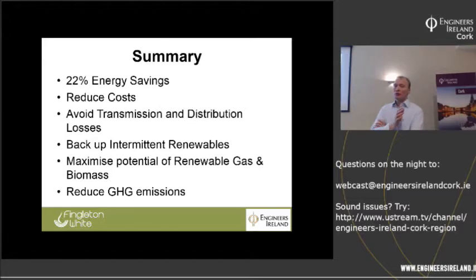If you're talking about the kind of processes we work on, they're very heavy heat loads that have been in existence for decades. Once you have that data about the operation of the plant you're looking at, if a site has steam metering, that's great. If not, you can look at gas bills, boiler efficiencies, and run hours. There are ways of analysing the heat loads that are very doable, not particularly challenging. The industrial heat loads are very easy to quantify, but variability, like a seasonal heat load, becomes more challenging.